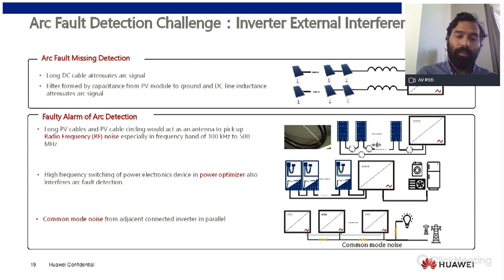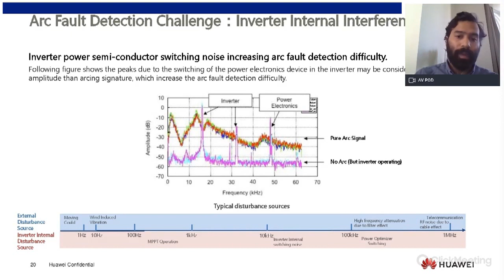There are also internal factors. Modern inverters are moving away from being just pure converters, DC to AC, to high power electronic equipment. There is a lot of high frequency switching. This will create a lot of noise as well. As you can see in this image, the signal from a pure arc and the signal within an inverter working in a normal situation will have some peaks because of the switching that could interfere with the arc signal and could lead to a false arc. Some of the common internal disturbances are the MPPT operation, the switching noise from components like IGBTs, and optimizer switching in the case you have them. So again, this is a challenge that the manufacturer needs to take into consideration when developing AFCI capabilities.